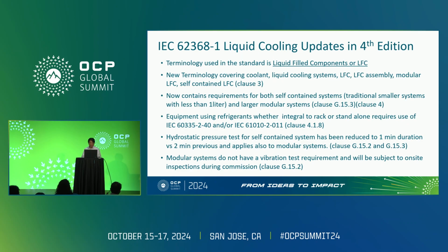They also have items for hydrostatic pressure tests for self-contained systems. It's reduced to a 1 minute duration versus the 2 minutes they had before. They just thought that 2 minutes was a little bit too long, so they reduced it. So again, you can see a number of things where they are just refining and clarifying so it's more relevant to the systems that are being sold today. They will probably keep looking at this area because they know there's a lot of activity going on and technology is evolving. So this is a good thing.